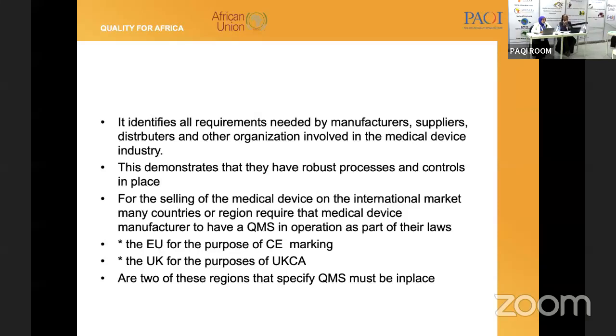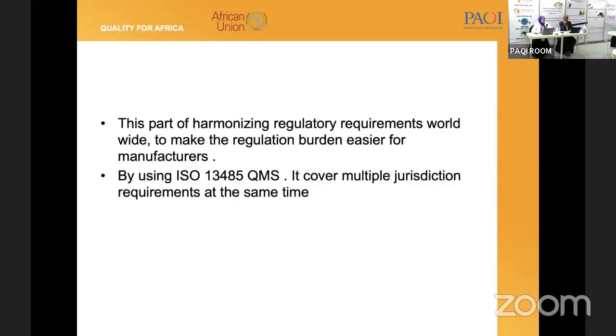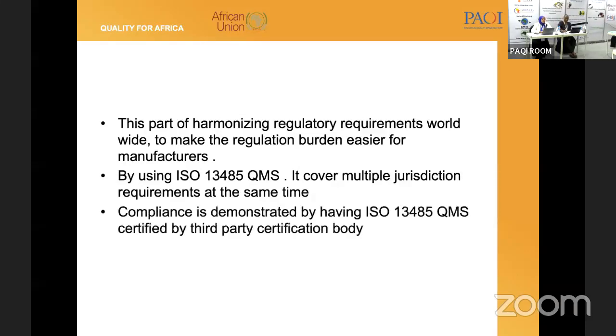For the selling of medical devices in the international market, many countries require that the medical device manufacturer have a quality management system in operation as part of their law, like the EU for the purpose of the CE mark and the UK for the purpose of the UK CA mark. This is considered part of harmonization of regulatory requirements worldwide to make the regulatory burden easier for the manufacturer. By using ISO 13485, it covers multiple jurisdiction requirements at the same time. Compliance is demonstrated by having an ISO 13485 quality management system certificate from a third-party certification body.